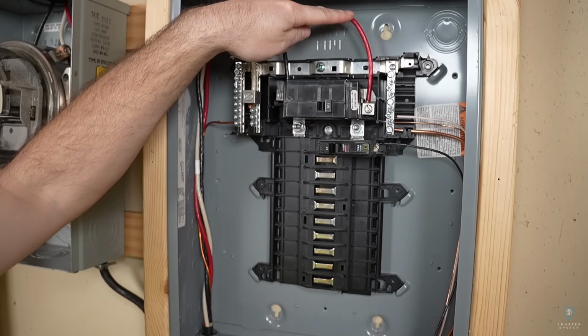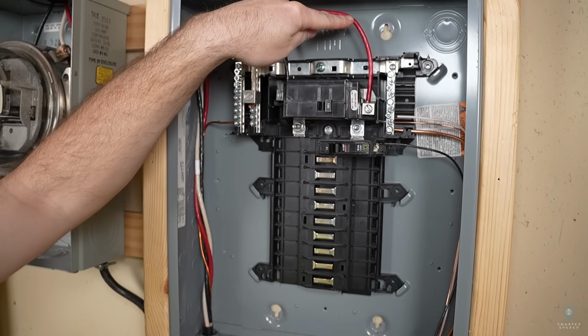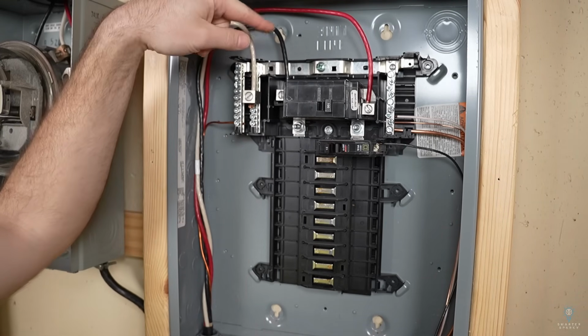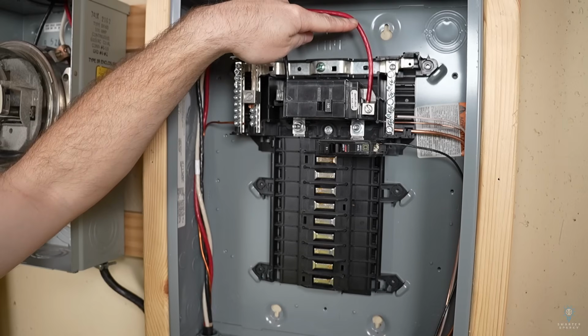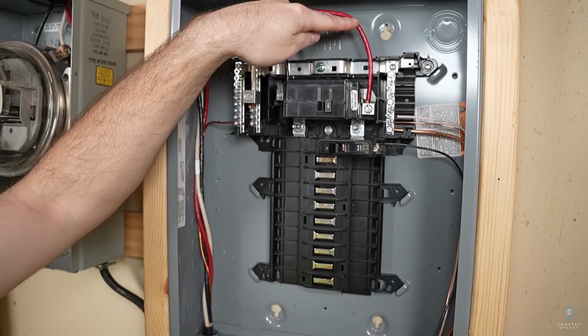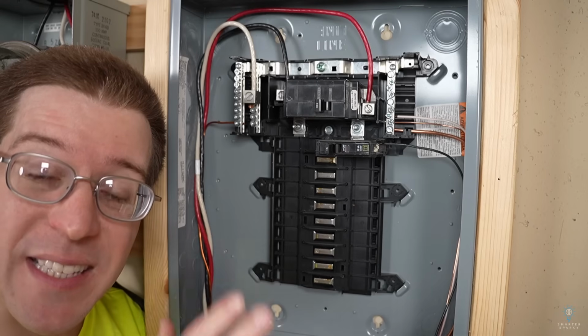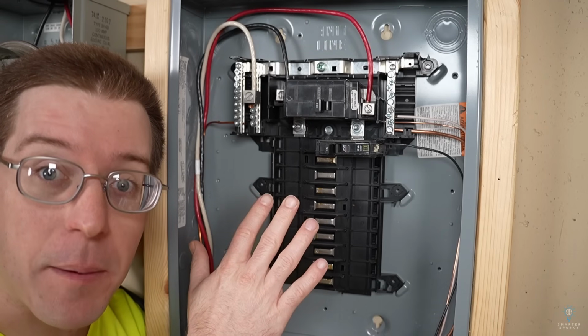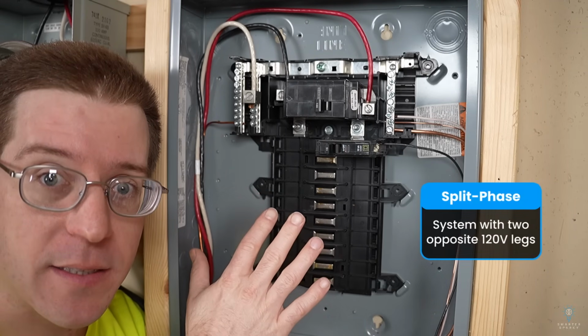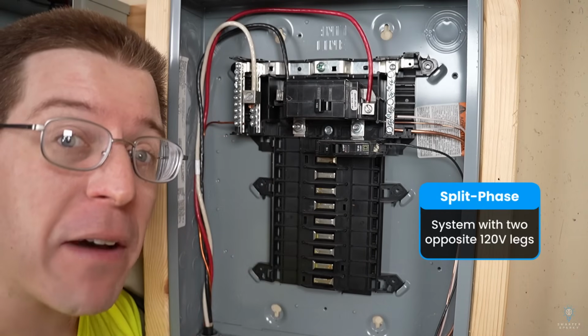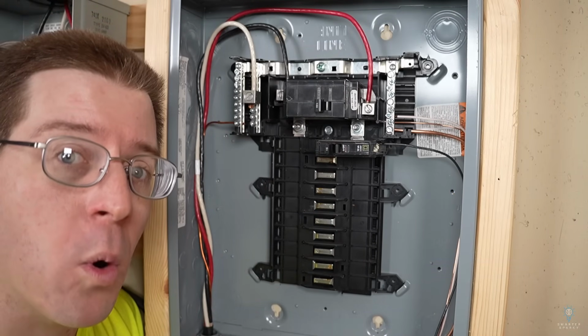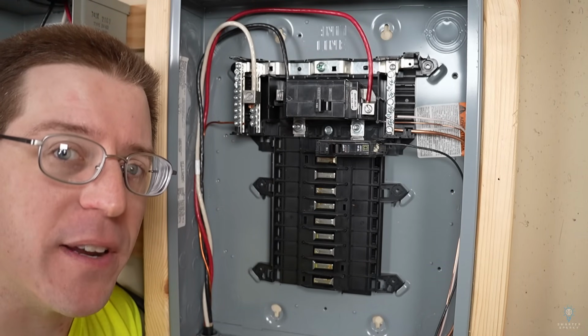These two hot conductors are called line 1 and line 2. Sometimes they're also called phases, phase A and phase B, or the black and the red phase. But don't let this confuse you. This is not a two-phase system. This is a split phase system. Each line is essentially half of a phase. We'll actually cover this more on a dedicated split phase video in the future.